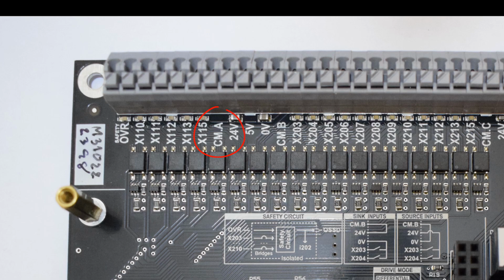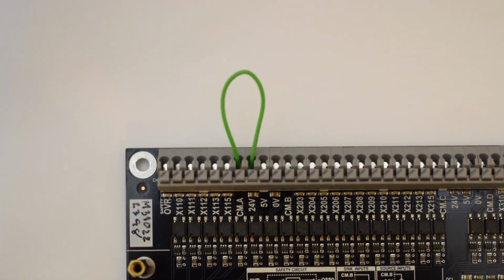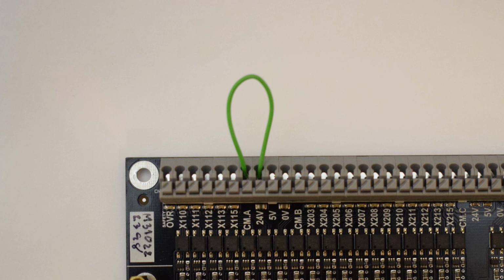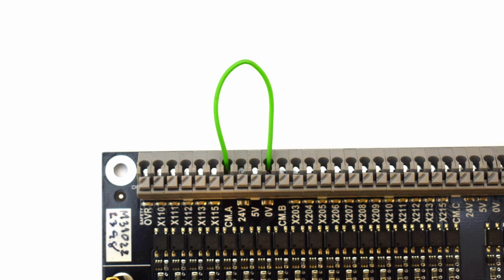So the CMA that you see is actually common A, and then common B, common C, and common D. Now, to make an NPN input, we would join the common A with the 24 volts. Now, to make a PNP, we would cross or join together the common A with the 0 volts.